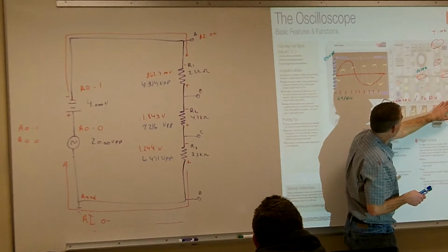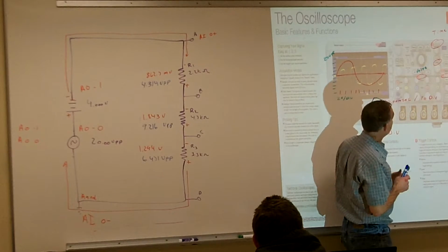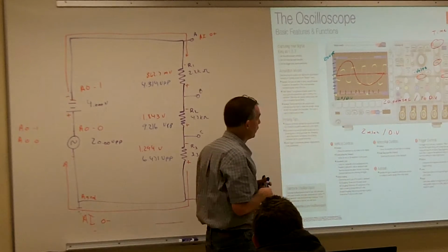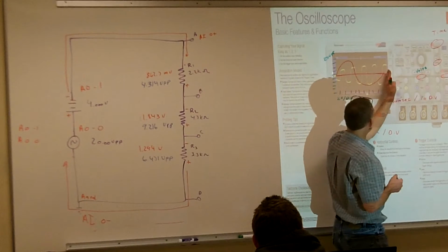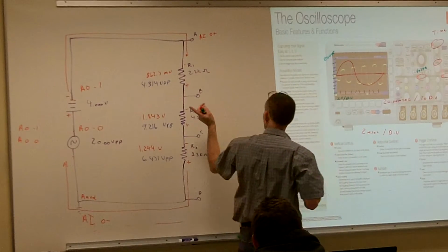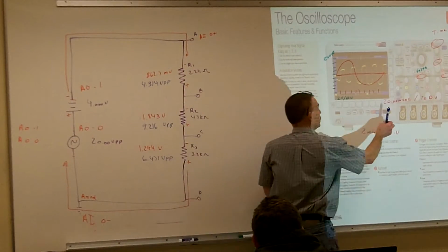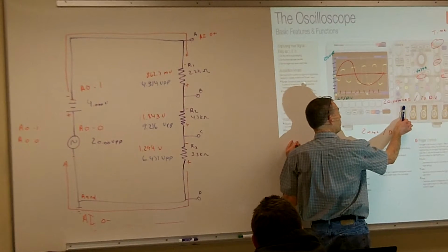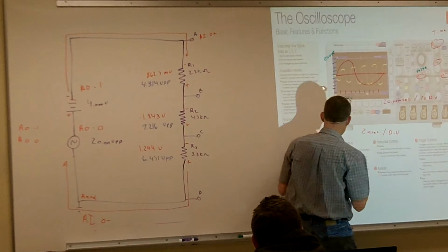The third one is our trigger. This is where people get kind of confused on setting up their trigger. Since this is a graphical representation of the sine wave, of what we're actually getting out on our test point, we have to tell the oscilloscope when to start to draw. And that's where I deal with my trigger.